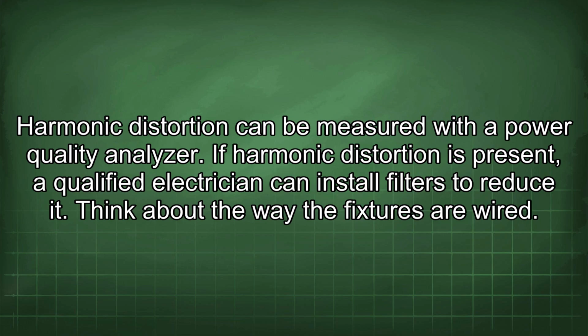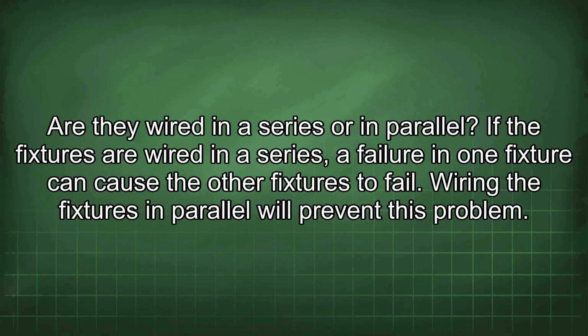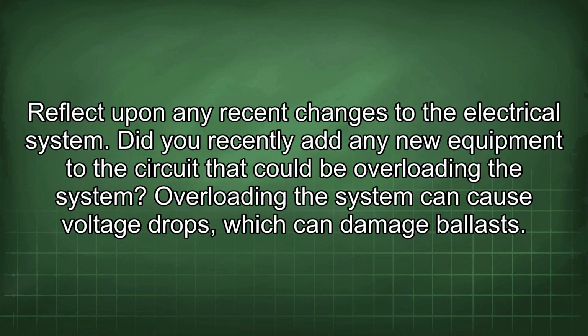Think about the way the fixtures are wired. Are they wired in a series or in parallel? If the fixtures are wired in a series, a failure in one fixture can cause the other fixtures to fail. Wiring the fixtures in parallel will prevent this problem. Reflect upon any recent changes to the electrical system. Did you recently add any new equipment to the circuit that could be overloading the system? Overloading the system can cause voltage drops, which can damage ballasts.